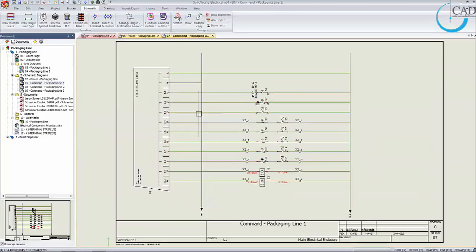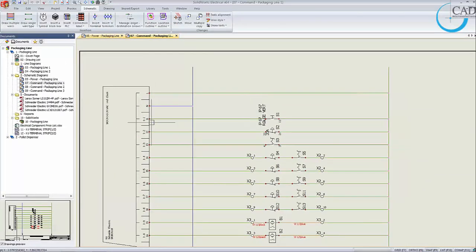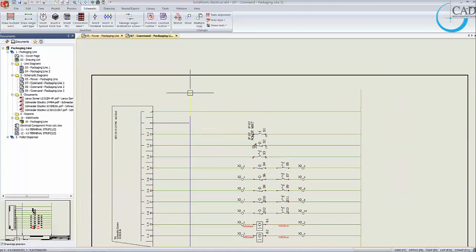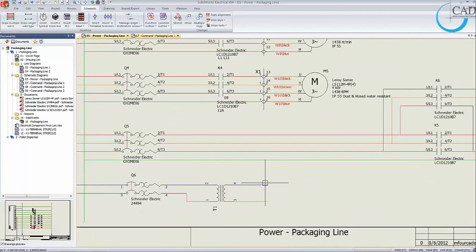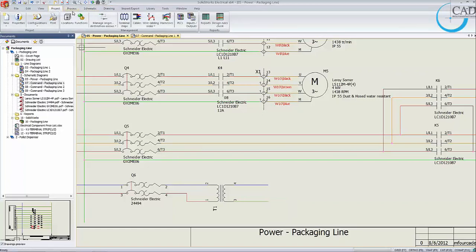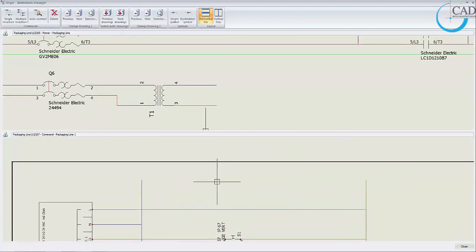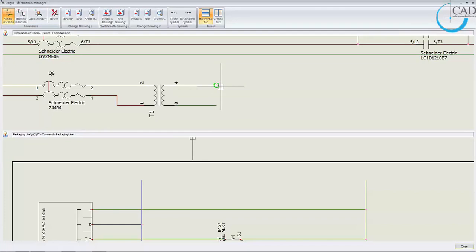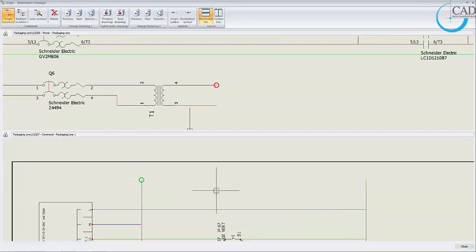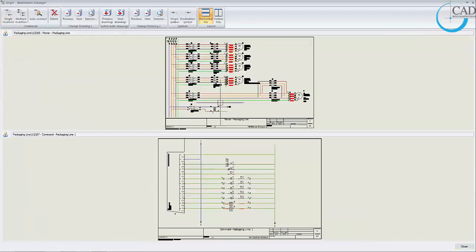If you open sheet 07, there is a PLC symbol with a blue line and a green (neutral) line which we'd like to connect to the lines from the transformer. This is done using something called origin-destination. We'd like to connect the blue line to the blue line. Use a single insertion and choose the origin. SOLIDWORKS Electrical has the intelligence to recognize wire equipotentials and only allows you to choose origin-destination of the same equipotential wires, avoiding unnecessary errors.